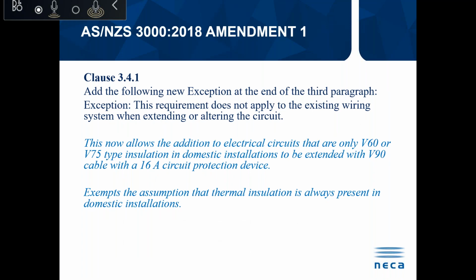In clause 3.4.1, they added the following new exception to the end of the third paragraph. Exception: this requirement does not apply to existing wiring systems when extending or altering the circuit. This now allows for the addition to electrical circuits that are only V60 insulation or V75 type insulation in domestic installations that can be extended with a V90 TPS insulation cable with a 16 amp circuit protection device.